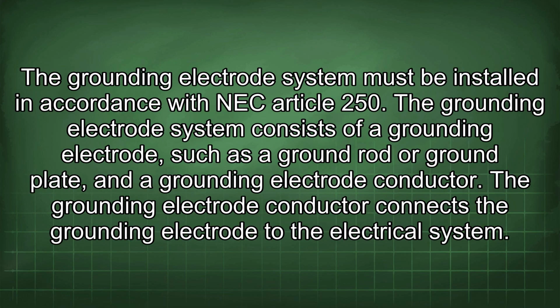The grounding electrode system must be installed in accordance with NEC Article 250. The grounding electrode system consists of a grounding electrode, such as a ground rod or ground plate, and a grounding electrode conductor. The grounding electrode conductor connects the grounding electrode to the electrical system.